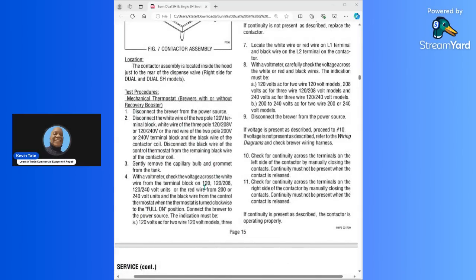Test procedures: mechanical thermostat, brewers with or without recovery booster. Disconnect the brewer from the power source. Disconnect the white wire of the 2-pole 120-volt terminal block, white wire of the 3-pole 120/208 volt or 120/240 volt, or the red wire of the 2-pole 200 or 240 volt terminal block, and the black wire of the contactor coil. Disconnect the black wire of the control thermostat from the remaining black wire of the contactor coil. Gently remove the capillary bulb and grommet from the tank.